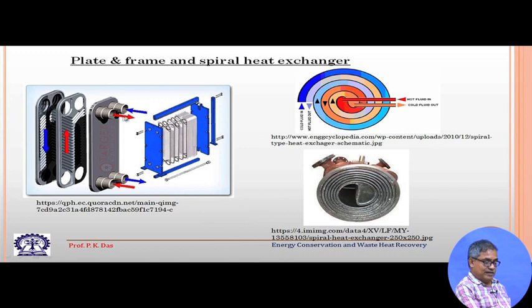Cleaning is very easy because you can open it, each and every plate you can clean, and then different arrangements of fluid flow can be made. And again, this is one design of heat exchanger which is very flexible, in the sense that if we require, we can increase the size of the heat exchanger by simply adding more plates, or we can reduce the size of the heat exchanger. So, this is a very unique design.